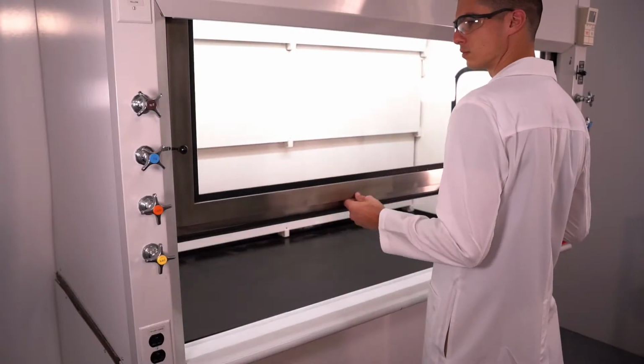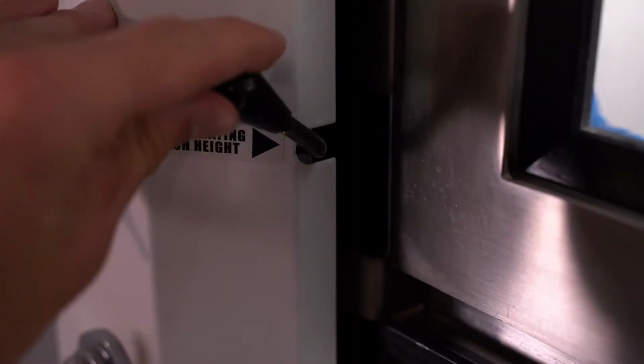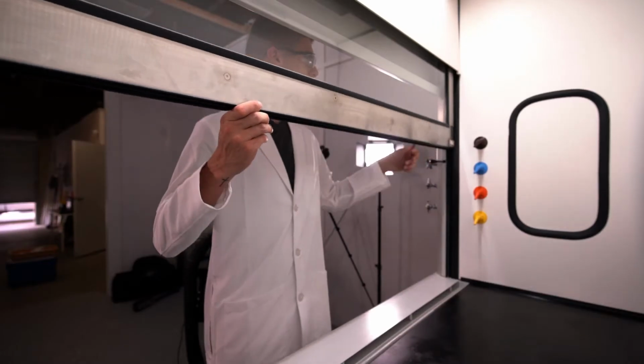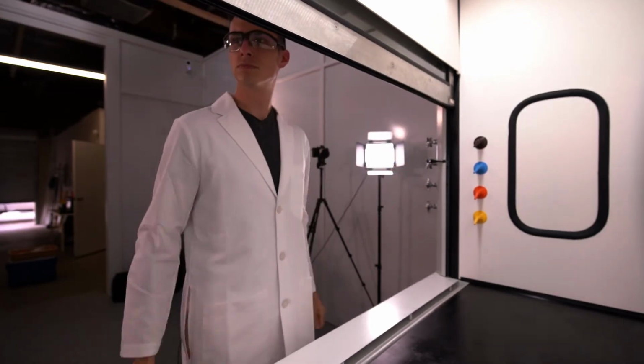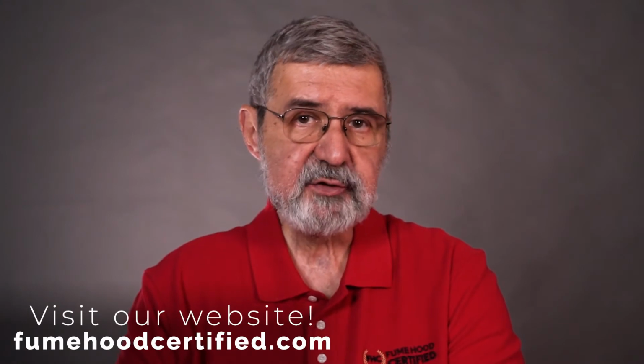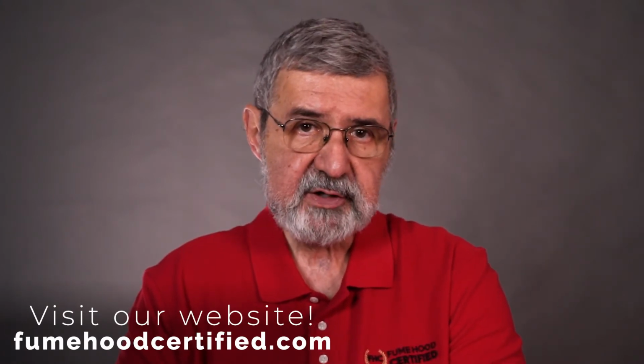The sash movement should be easy. Many sashes can be operated with one hand from any position along the sash handle, and many newer hoods often have auto sashes that move with the assistance of a motor. Hood sashes are generally made from some type of safety glass, either tempered safety glass or laminated safety glass. This safety glass is used to offer you more protection and to minimize the likelihood of the sash itself breaking and becoming part of an incident.